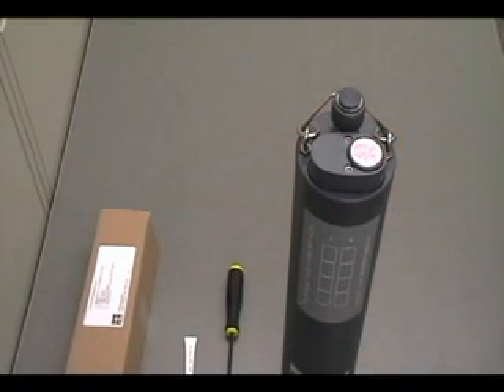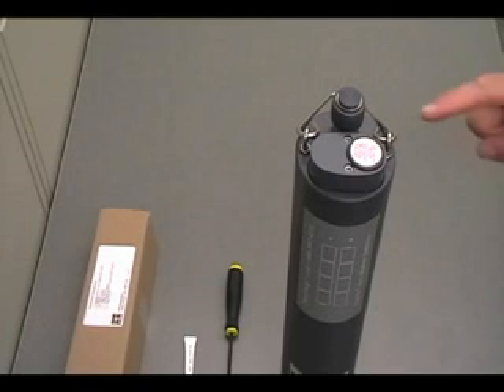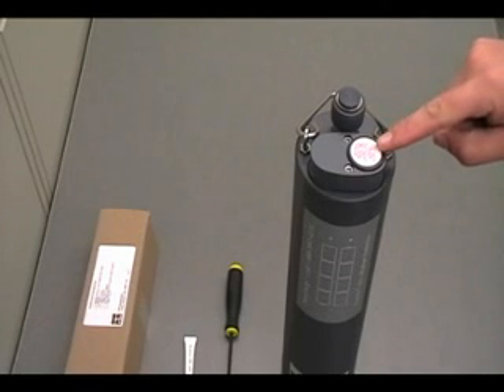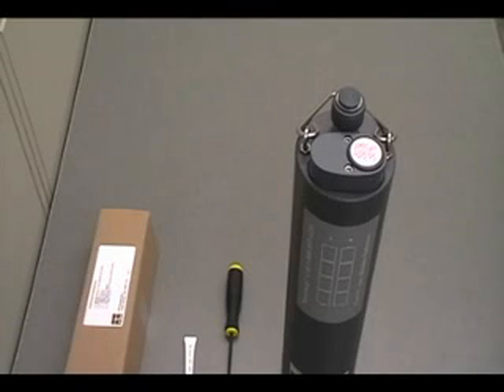Remove batteries from the sonde when not in use, for example, for long-term storage. The battery compartment of this sonde has a lid with a round pressure release safety valve. In the highly unlikely event that the batteries should malfunction and degas, this valve will release any pressure building up in the battery compartment. If the valve ever opens, the battery compartment lid must be replaced with a new one from the manufacturer before the sonde can be used again.